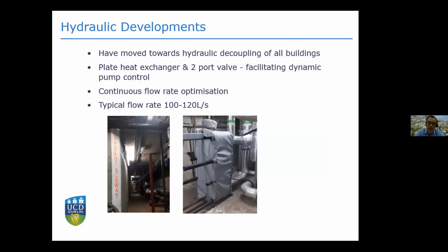We've generally moved towards hydraulic decoupling of all buildings. Initially that wasn't always the case, but the picture to the left shows a typical subway, which brings the district heating pipes from the main spine into a building plant room. The picture to the right shows what you'd be presented with in a plant room - we have a plate heat exchanger in some buildings.